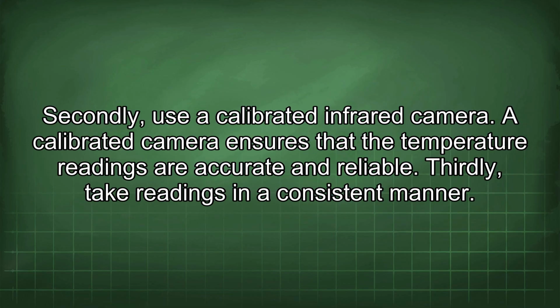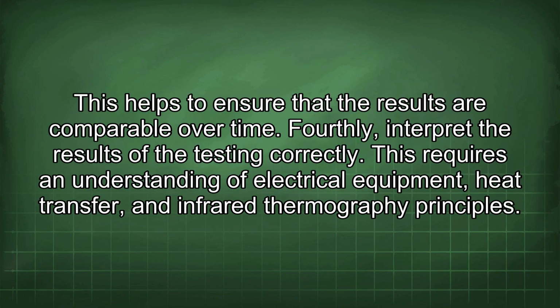Secondly, use a calibrated infrared camera. A calibrated camera ensures that the temperature readings are accurate and reliable. Thirdly, take readings in a consistent manner. This helps to ensure that the results are comparable over time. Fourthly, interpret the results of the testing correctly. This requires an understanding of electrical equipment, heat transfer, and infrared thermography principles.